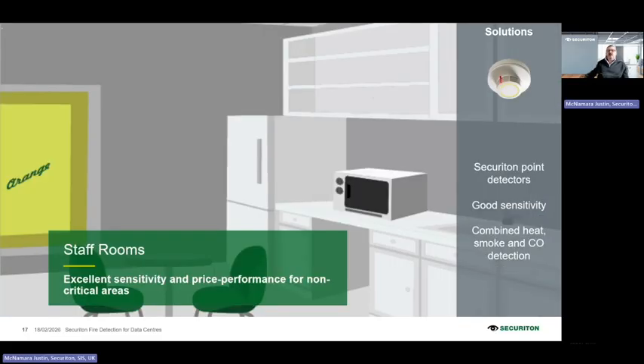In almost my last couple of sections, just talking about the different areas in a data center - briefly on staff rooms, as I mentioned, there'll always be a room where on-site personnel can gather. We need to make sure we've got a good, normal detection system. You'll see in a later slide a range of smoke detectors and a very high level, clever fire panel, FACP, that's able to control the entire system, including all the devices I've mentioned thus far - the aspirating detectors, the ADW, etc.